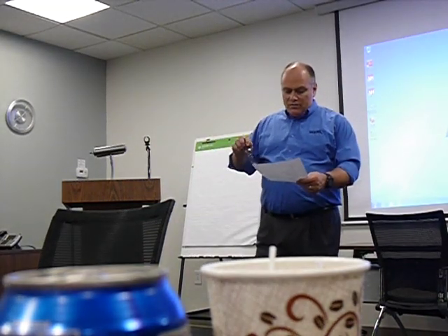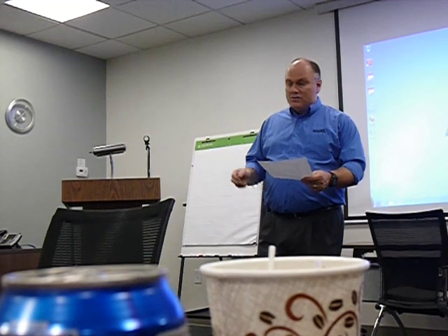Months, depending on how often a laboratory uses it. It doesn't need to be changed out every single PM cycle, preventive maintenance cycle, but you do need to look at it and inspect it every time you crack one of these open. A lot of times it gets dirty inside, depending on the buffer solution we're using, a lot of spillage, so clean a little bit of that up. But he's going to go over all these things: troubleshooting, volumetric calibration, temperature calibration.